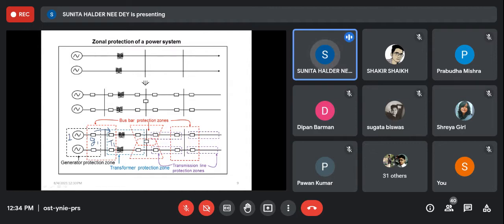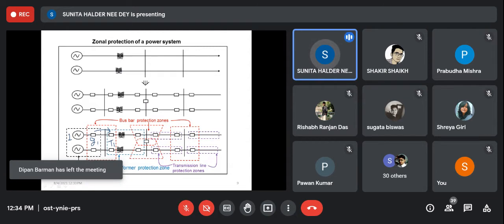So if there is a fault in generator 1, then the G1 relay is providing direct protection. The G1 relay is the relay connected with G1, the G1 protection system. G1 here obviously means a circuit breaker along with a relay. So G1 is called the primary relay, that is, it is primarily given to protect generator 1. Secondly, T1 will act as a backup relay. If G1 fails, then T1 will give secondary protection to generator 1. At the same time, T1 provides the primary protection for transformer 1, right?